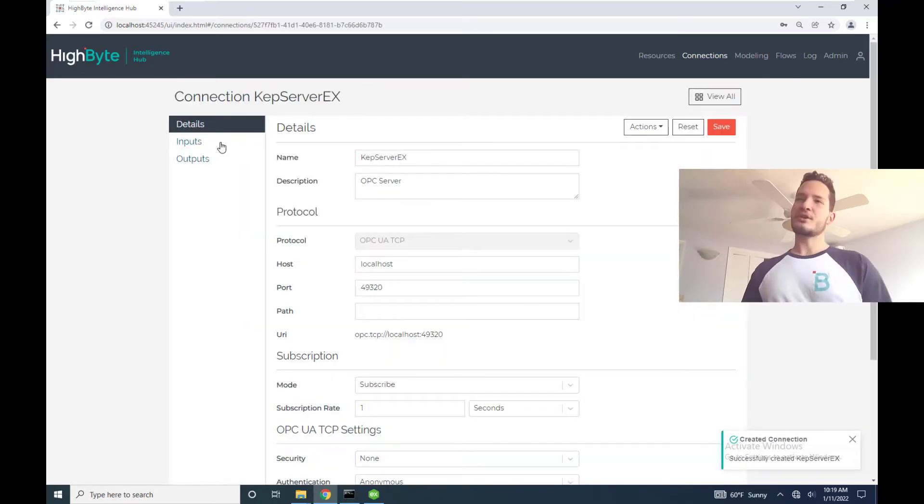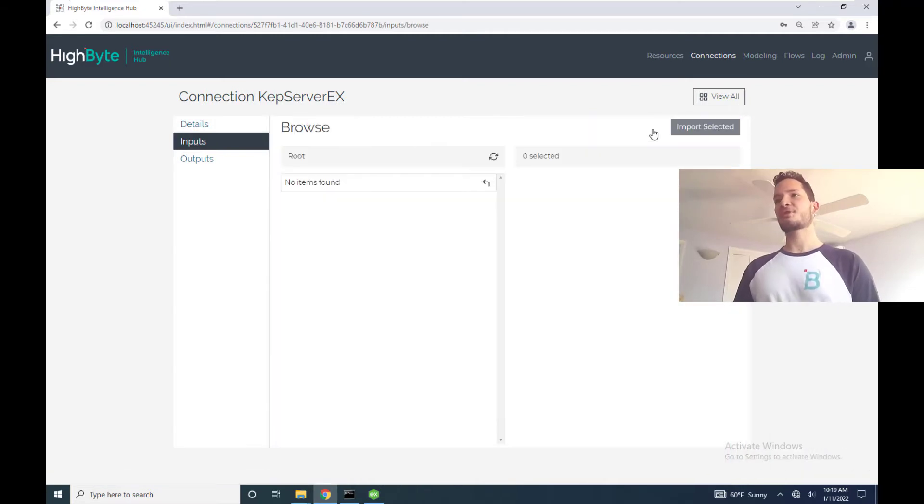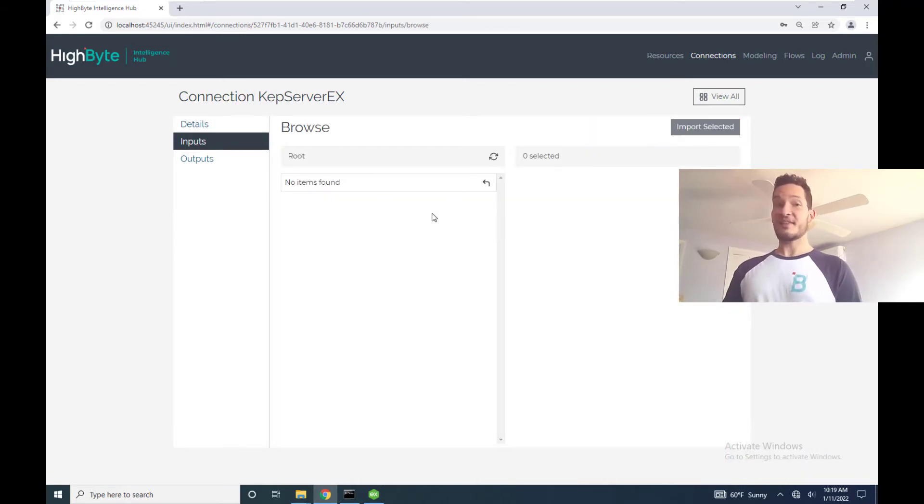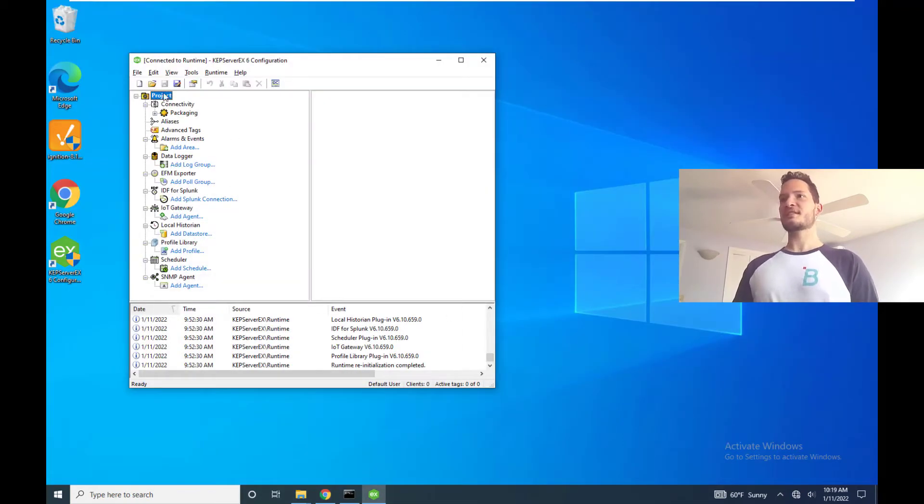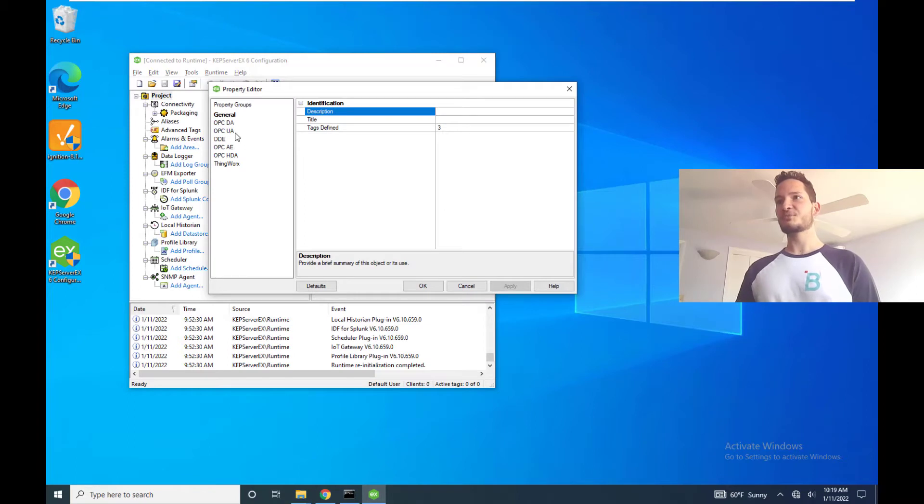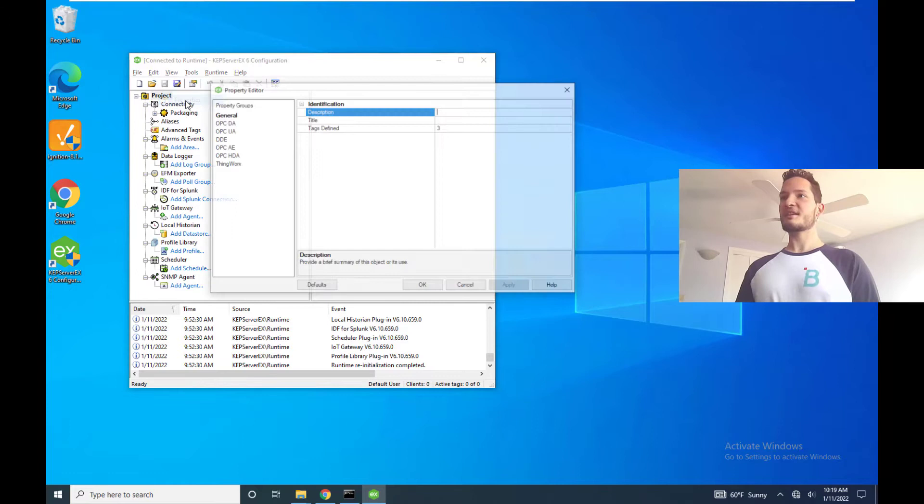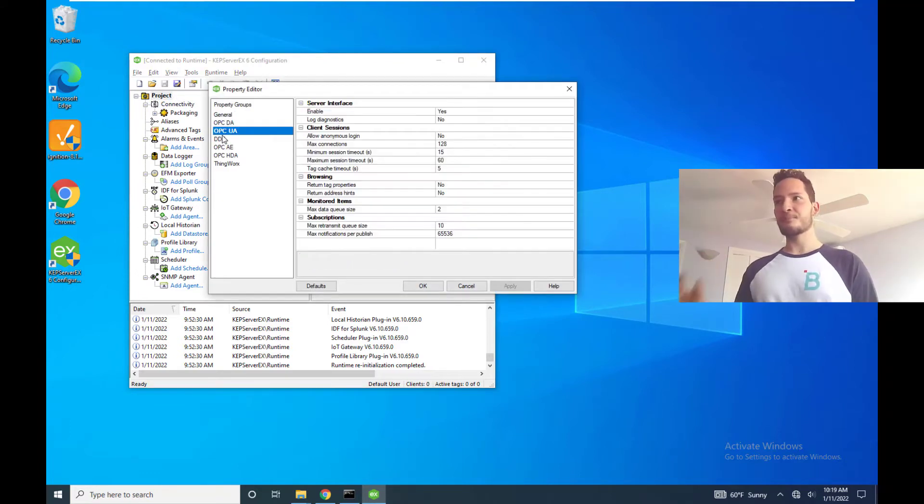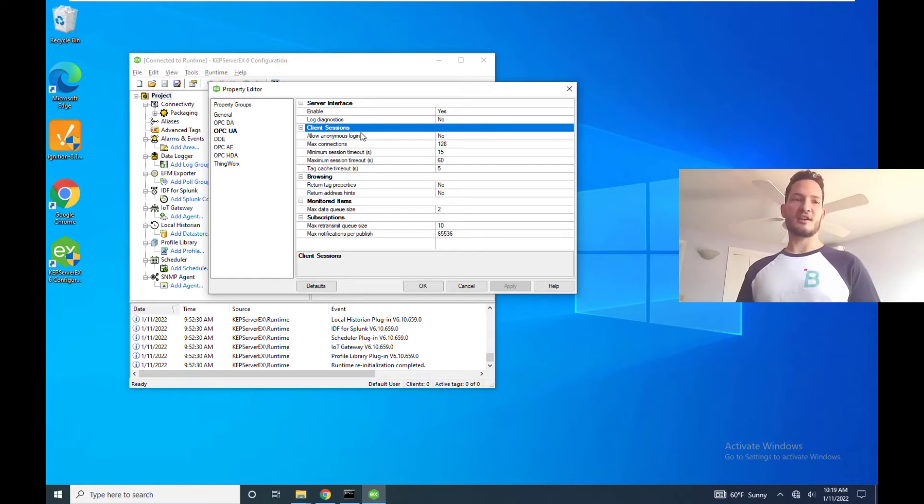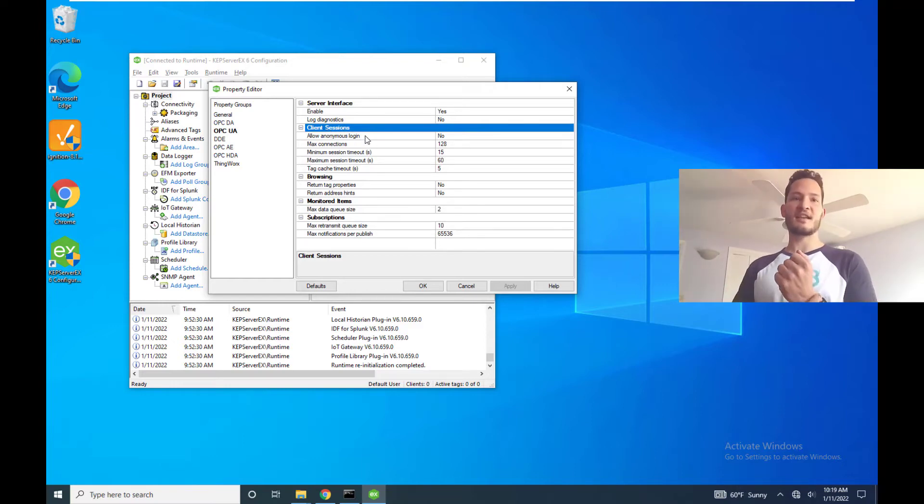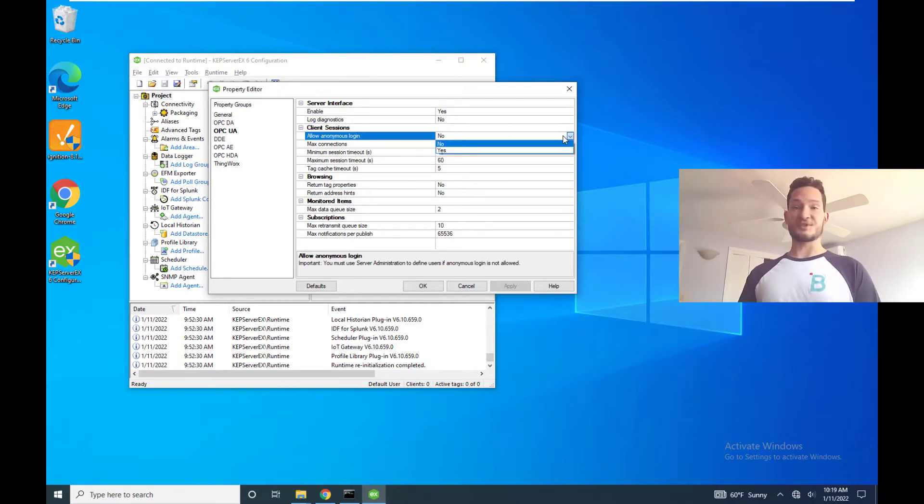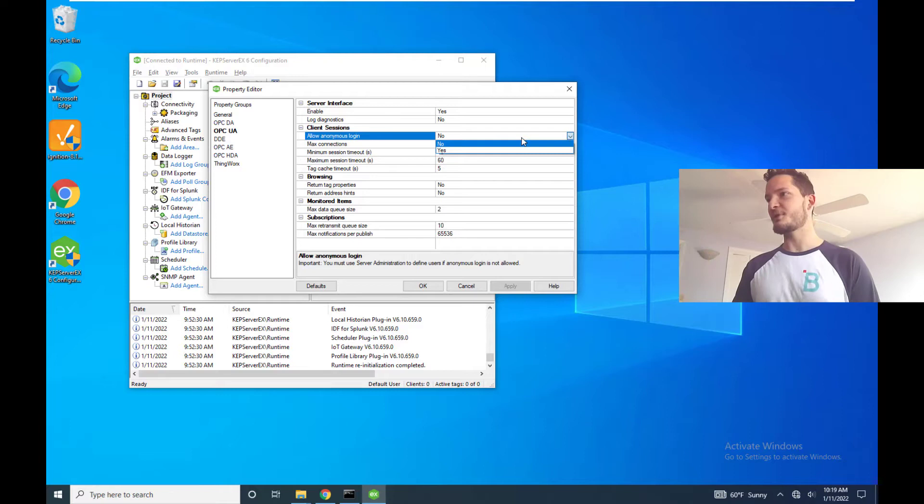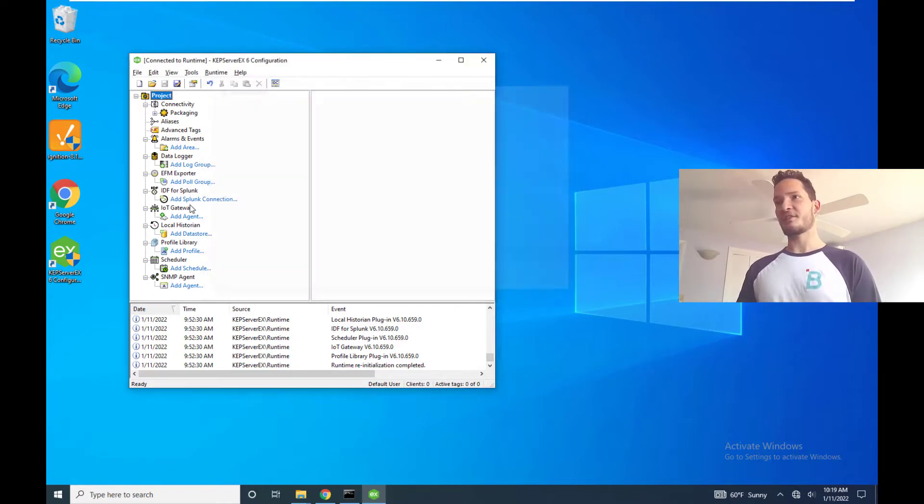So now you might think that I would be able to browse to my Kepware server at this point but nothing is pulling up and that's actually by design. So if we go back to our Kepware server we can see that there is this setting. I right clicked on project, went to properties and then went to OPC UA. Now Kepware server by default locks down anonymous login so that you cannot get in as an anonymous client which is good in general case right? That's a good secure policy. For our purposes today we're going to disable that. So I'm going to say yes you can allow anonymous login and then click OK on this.